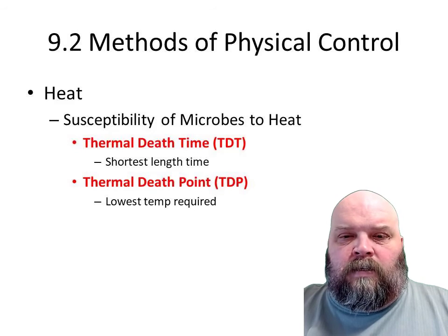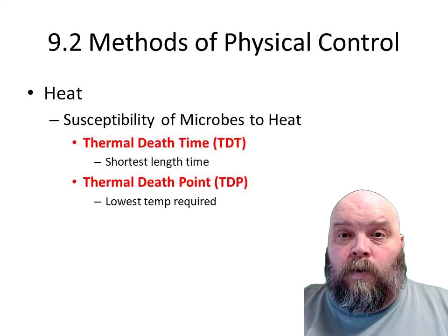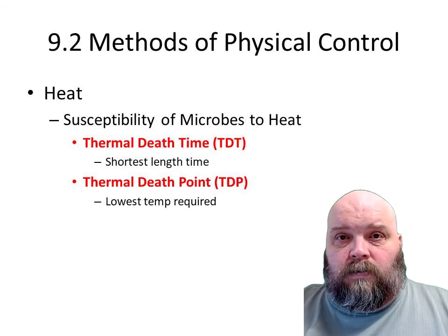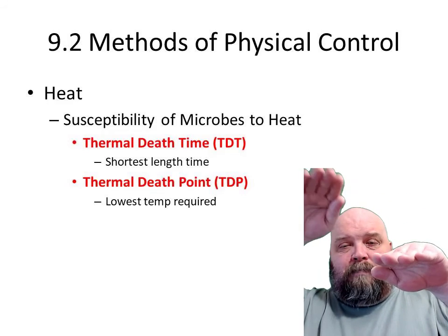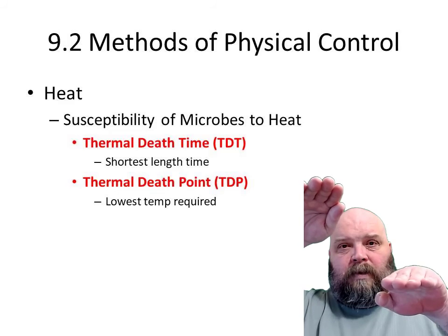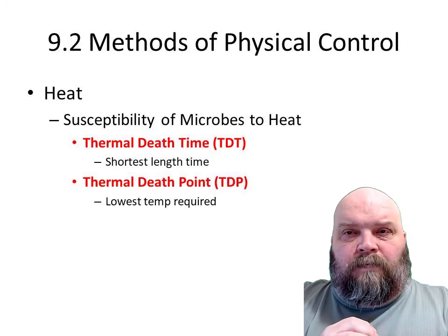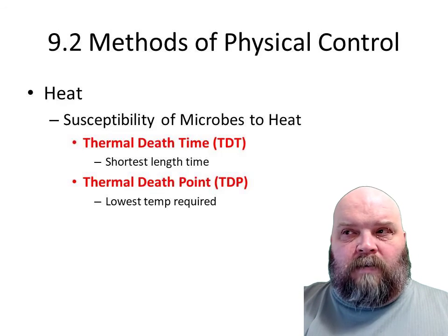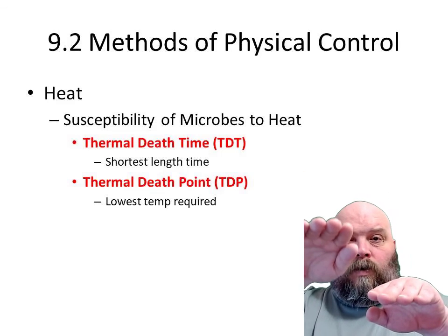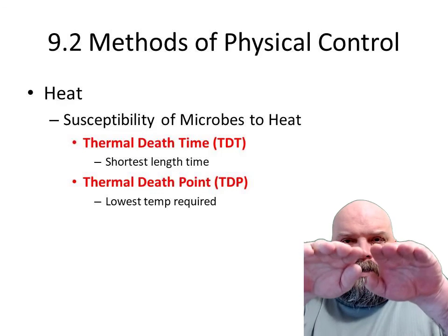Death time, shortest length of time; death point, lowest temperature. It's a balance. Higher the temperature, lower the time. But the higher the temperature, the greater the chances of damaging whatever object, whatever instrument you're trying to decontaminate or sterilize. So if you lower the temperature, you have to increase the time. It's a nice balance.